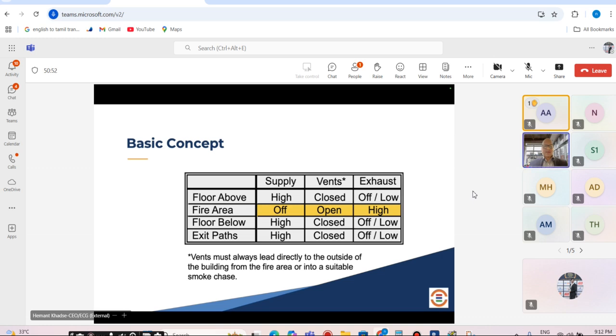If the fire floor has a lobby which is also pressurized, you can also do that by creating the pressurization active on high mode, at the same time with the vent closed. So you have various combinations, and again, there is no cast-in-concrete rule that can be addressed by any codes or standard that this is the most applicable strategy for your facility. It is purely the engineer's purview how you are going to implement this particular logic and build it into the system so that it becomes your own engineered system.